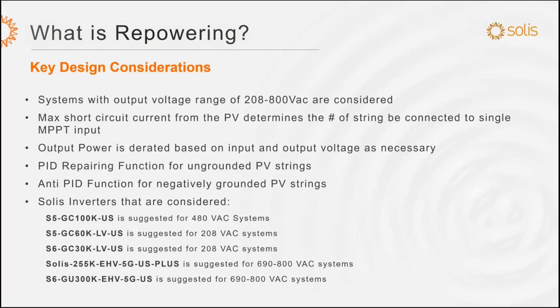PID repair function for ungrounded PV strings. Those new inverters all have built-in PID recovery, which is PID during nighttime, which could recover some of the degradation caused by PID on the current modules. Also, some inverters have an anti-PID function for negatively grounded PV strings. If you have an application where the grounding must be negative, we can use the anti-PID function to pull the ground potential above minus PV potential, and therefore achieve the same result as a grounded system.